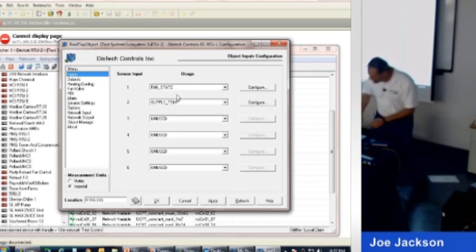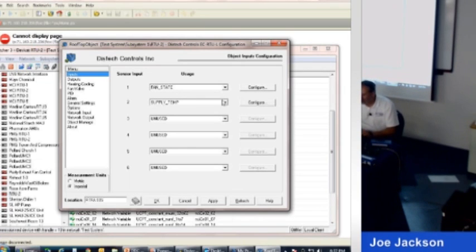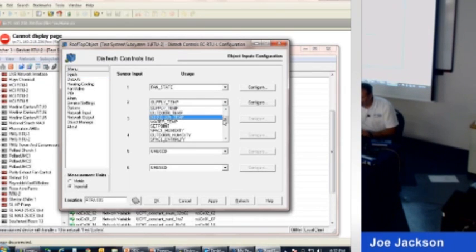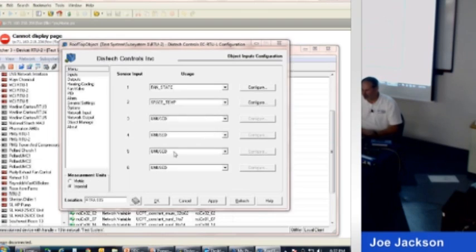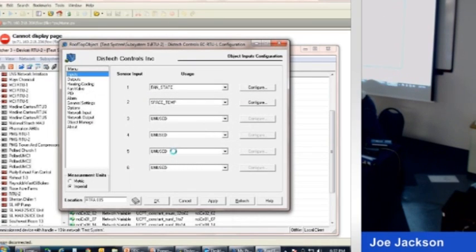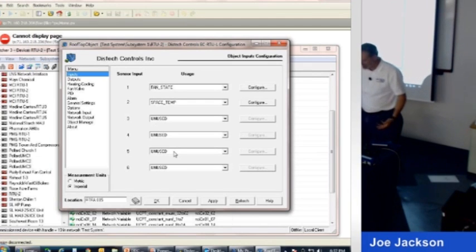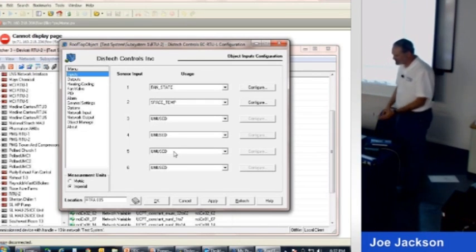Temperature, room temperature. Actually, that next one I missed. Space temperature. So we could grab one of these little $30 sensors. They're available with lots of options. This one has an override button. You could get it with a set point. Maybe you don't want them to be able to adjust it. Maybe you only want to do that through the computer. So we're going to have a fan status and a space temperature.